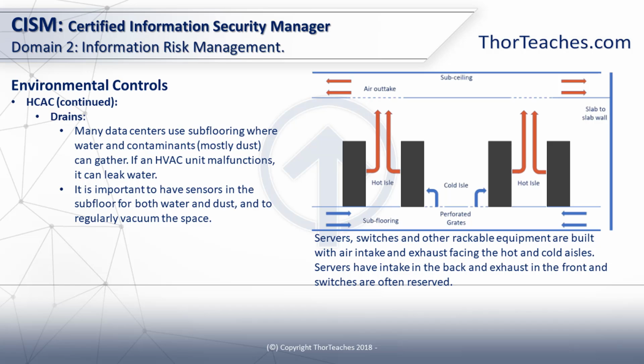And how we keep the airflow is critical too. If we just had perforated grates throughout the data center, we'd be pushing in the air all over the place and not where it's needed. We'd spend more money on power for our HVAC system, and the servers would have to work harder to keep within their optimal range of operations. So having the hot aisles and the cold aisles makes a lot of sense, both financially as well as operationally.